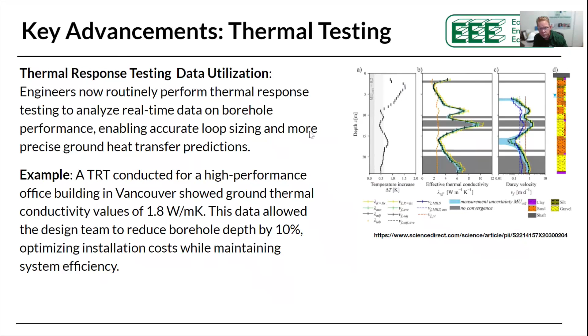So if you can calculate what the heat transfer is and what the performance is going to be, you can have a significant impact on your ground loop. For example, if we had thermal testing done and it comes in at 1.5 watts per degree change versus 1.8 watts per degree change, that can make a 10% difference in your ground loop design. So having these tests done is really important. There are a lot of great companies, certainly based out of Toronto, that do this borehole testing to make sure they're building a high performance building with a properly sized high performance ground loop to support it.